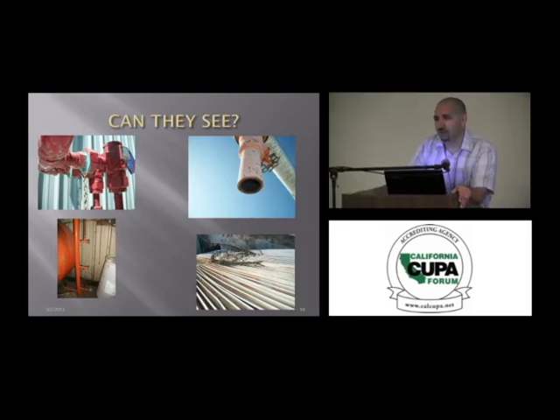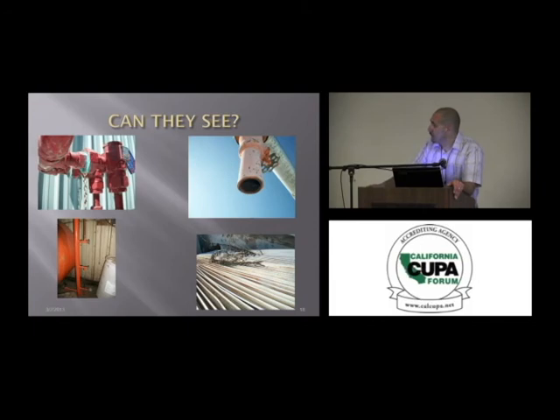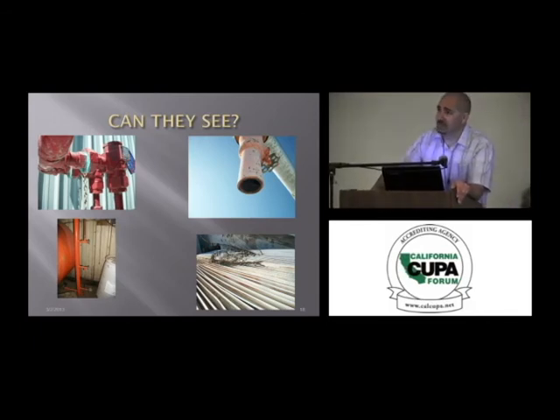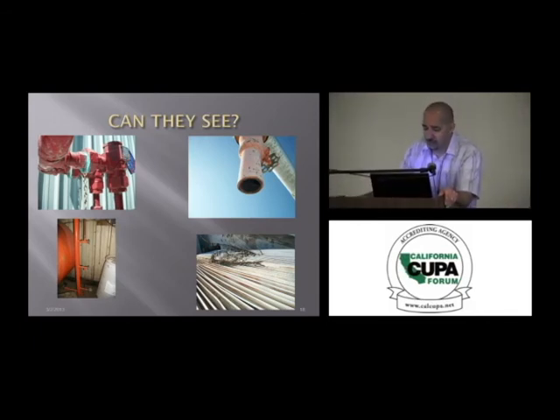It's probably hard for you to tell, but that is a sight glass. That is a very scary sight glass telling you the ammonia level inside of the high pressure receiver. That one was broken. And the high pressure receiver had ammonia. The little valves were isolated, but they didn't do anything about replacing it. It was broken, and I always make a recommendation when I see this to look into putting a sturdy bullseye column or just to remove.